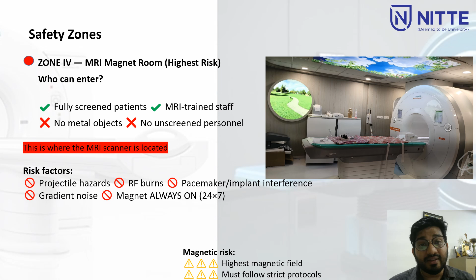Now we'll talk a bit about the 5 gauss line. It is the critical boundary mark where magnetic field strength begins to affect pacemakers, implanted medical devices and ferromagnetic objects. It typically extends several meters from the scanner bore. For 1.5T, the 5 gauss line distance is approximately 1.5 to 2.5 meters from the bore. In a 3 Tesla MRI, the 5 gauss line distance is approximately 2.5 to 4 meters from the bore. In 3T, the magnetic field is twice as strong. Also, we have to know about the fringe field, that is nothing but the magnetic field that leaks out of the MRI scanner beyond the bore. The fringe field expands outwards.